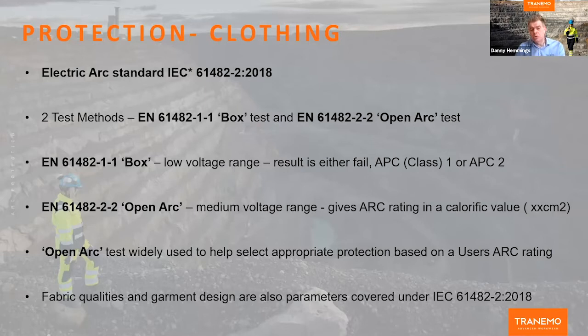The second test method, which is called open arc, works on a medium voltage range, and this gives a calorific value in the test data. And really the view is that it is a better way to assess the protection of a fabric or a garment, because as we talked about before, you want to be referring to the calorific value, the incident energy in calories per centimeter squared. The problem with the box test is it's really very subjective. It's either fail, class 1 or class 2, which makes it very difficult to create comparisons between product ranges or know really where you need to be from a protection point of view.